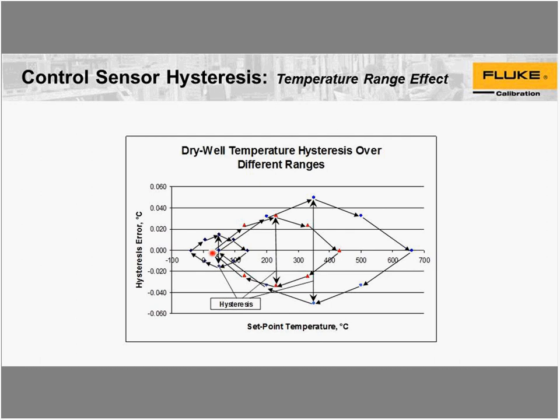And when you do this, by the way, whatever temperatures you decide to dwell at, it stabilizes, and you get a good average of that temperature at each point. Now, the minimum points will be at the bottom, top, and in the middle of that range.